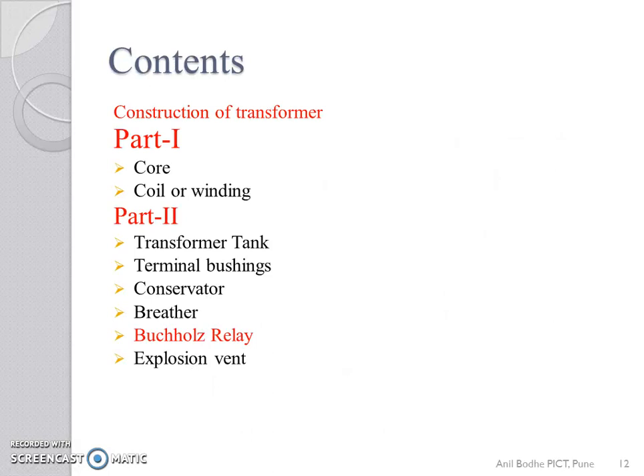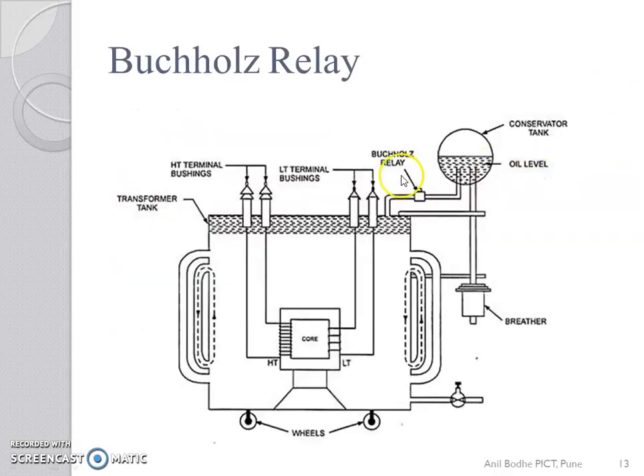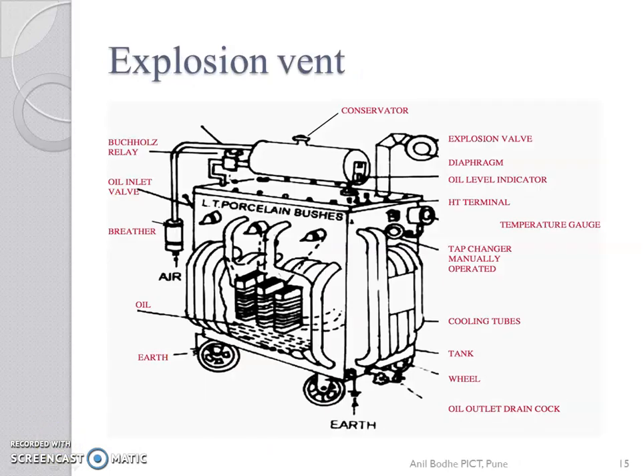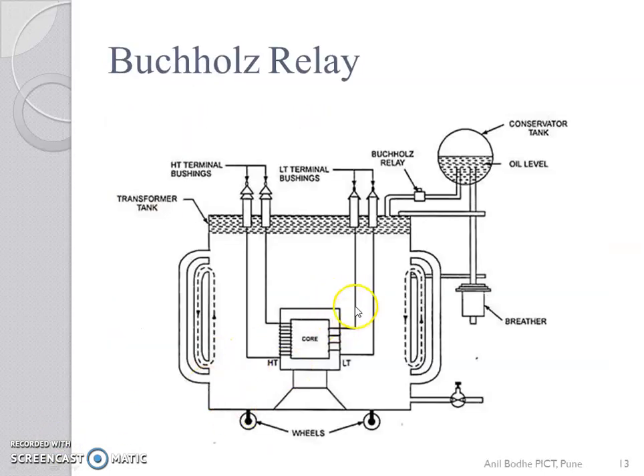Next, Buchholz relay. It is a type of protective device mounted in the pipeline connecting the main tank to the conservator tank. Due to the excessive heat developed during the fault condition, the oil in the tank in the vicinity of the fault point gets decomposed and different types of gases are liberated. These gases operate the Buchholz relay which in the initial condition gives the alarm to the operator. If the fault developed is converted into a serious type of fault, then this relay trips off the main circuit breaker.